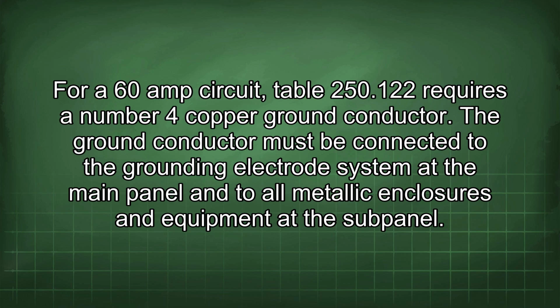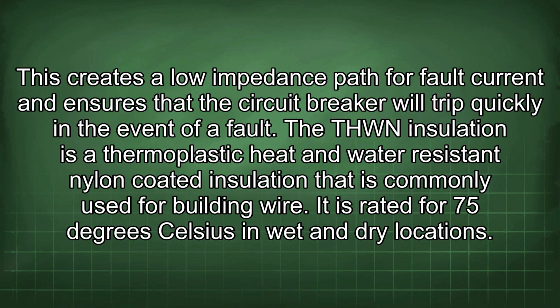The ground conductor must be connected to the grounding electrode system at the main panel and to all metallic enclosures and equipment at the subpanel. This creates a low impedance path for fault current and ensures that the circuit breaker will trip quickly in the event of a fault. The THWN insulation is a thermoplastic heat and water resistant nylon coated insulation that is commonly used for building wire. It is rated for 75 degrees Celsius in wet and dry locations.